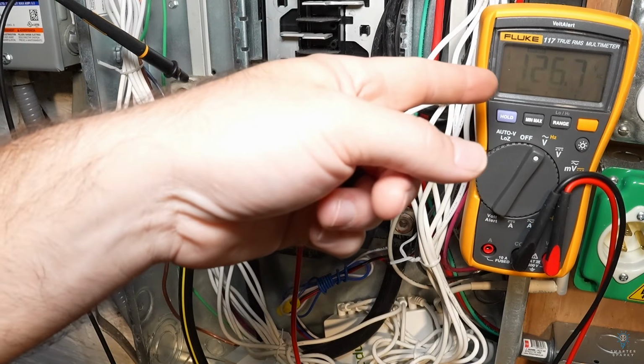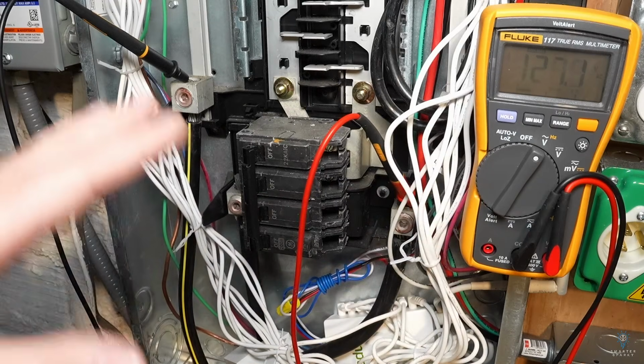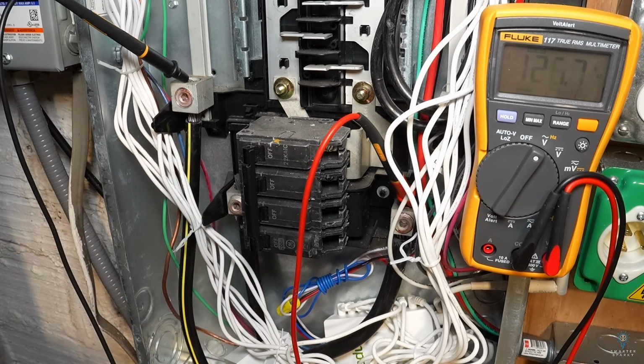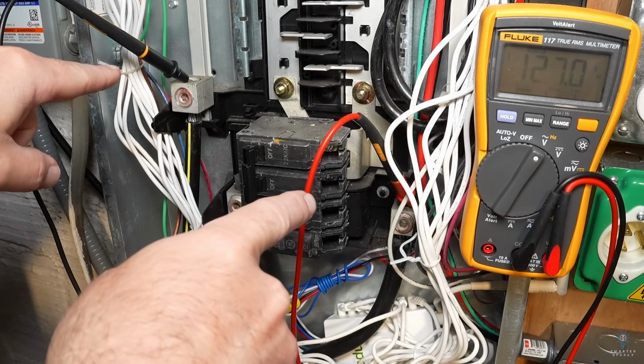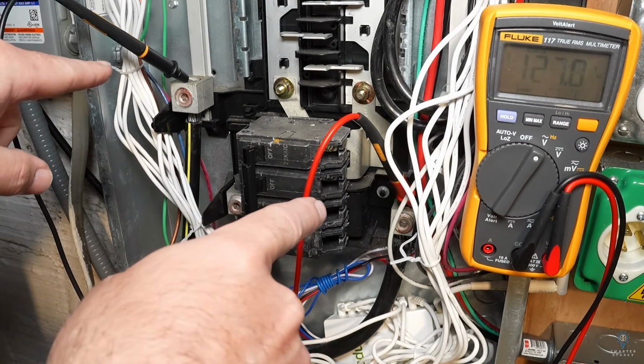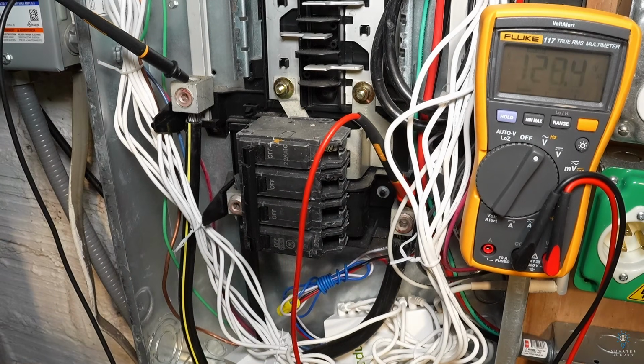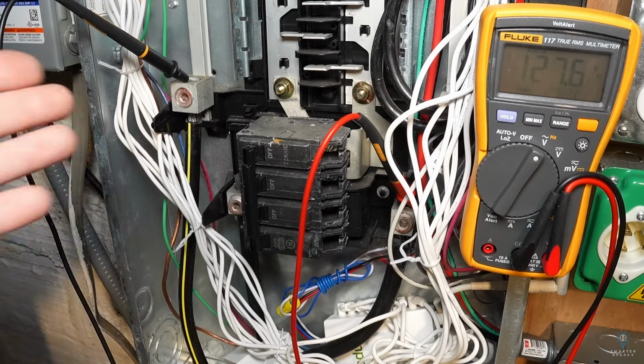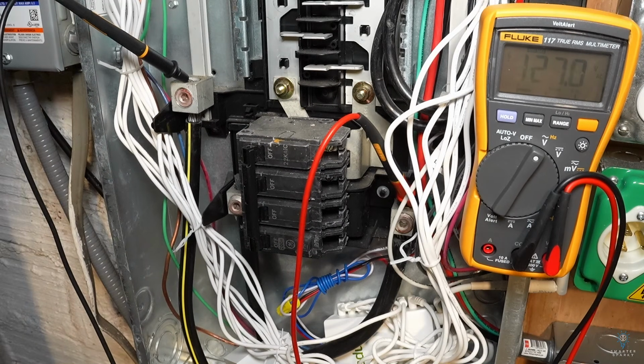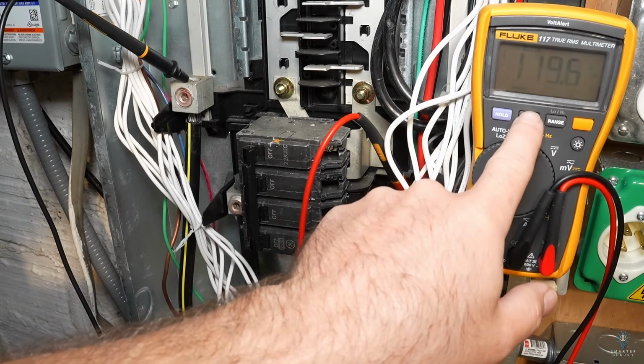The code says your voltage shouldn't deviate more than 3% on a branch circuit or 5% overall. So right now we are measuring right off the incoming power, which means our voltage shouldn't fluctuate more than 5% of 240 volts line to line or 120 volts from line to neutral. So it's been running for maybe 2-3 minutes now, so let's see what our values are.